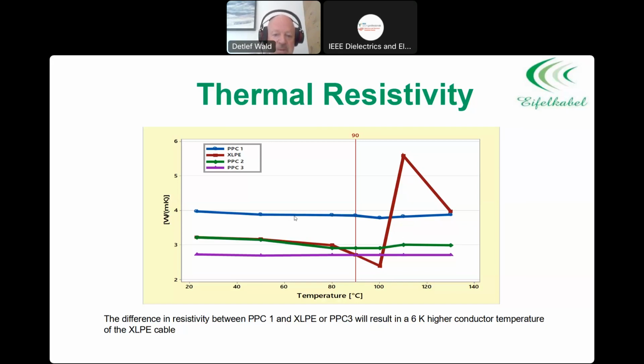The difference between the blue one and the XLPE will result in a 6 Kelvin higher conductor temperature at the same load. This was also confirmed in practice at 90 degrees. So there are solutions there, but it needs to be commercialized and needs to be further evaluated.